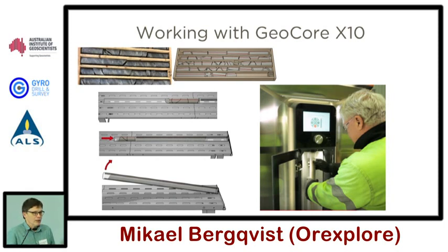And also it is more centrally located, and it can be not only older cores but cores from another campaign that can be put through that machine. So we insert up to 4 meters of cores at one time in 4 slots, and then push the button, and the machine will automatically scan the whole set of data.